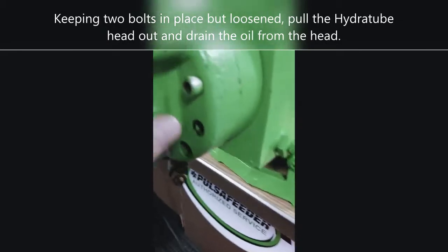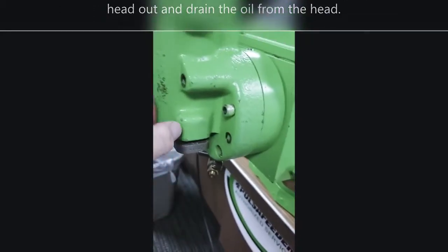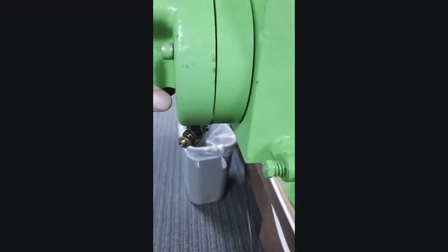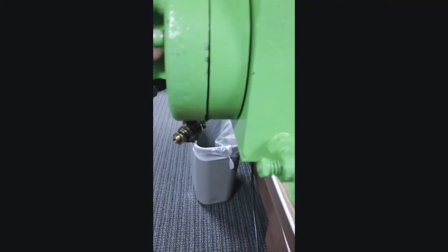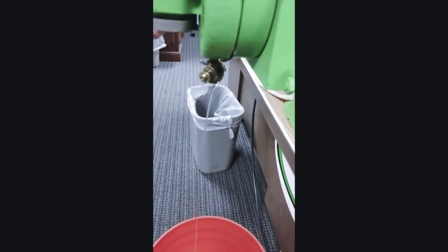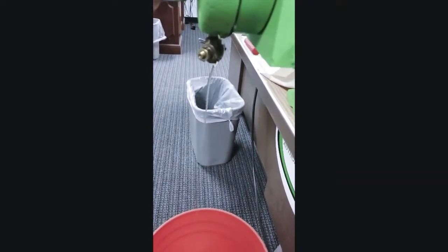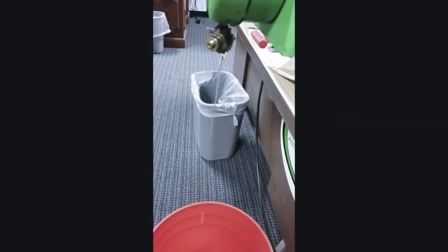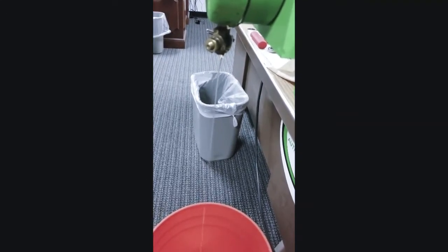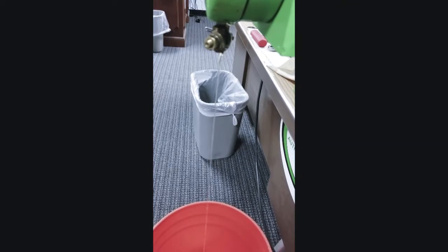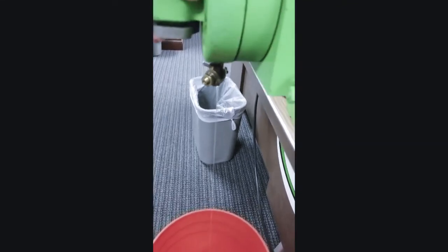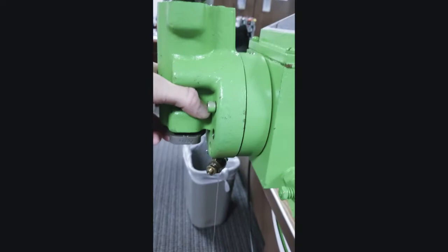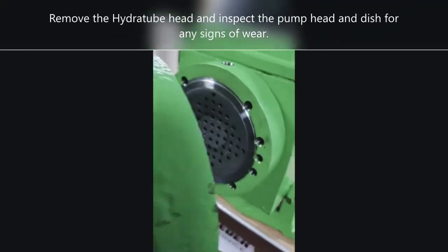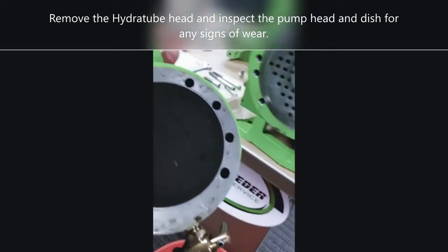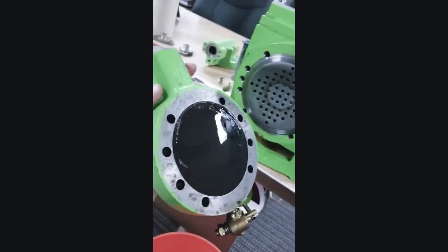Okay, I've gotten almost all of the bolts off except for the last two, and you can see I'm starting to drain oil. So what I'm going to do is just try to tilt that forward a little bit so that I can get the oil to run out the bottom of the pump as best as I can. And then once that starts to tail off, I will remove the head and we will start to break down the Hydratube head. Okay, I've taken the bolts off and I've now removed my Hydratube head.